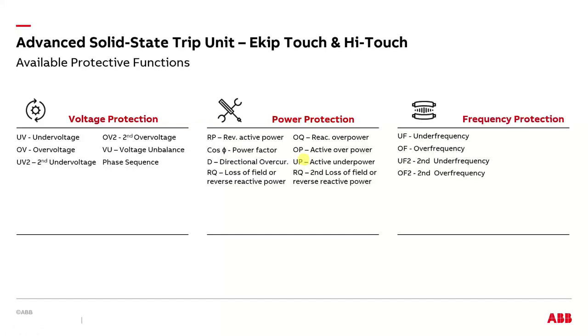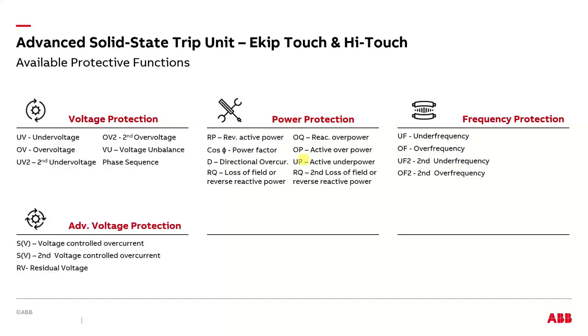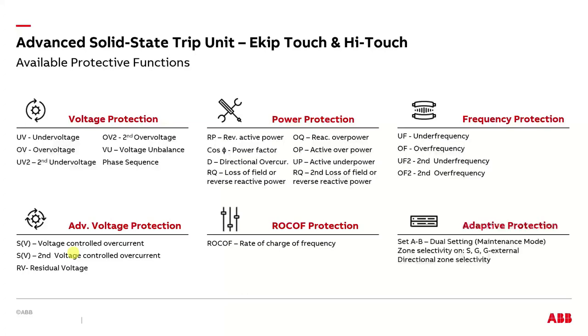So it's a huge jump in technology: frequency protection, advanced voltage protection, the voltage controlled overcurrent, which basically moves the overcurrent trip based on the restrained voltage. That would be good for a generator. A second one is voltage restrained overcurrent. ROCOF is rate of change of frequency. That would be good for generators and microgrids.